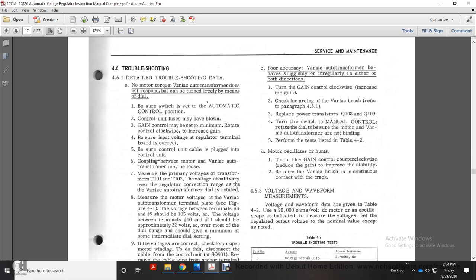Alright, troubleshooting. 4.6.1, detailed troubleshooting data. No matter the torque, variadic auto transformer do not respond, but they can be turned freely with the meaning of the dial. Be sure your switch is an automatic control switch. Control unit fuses may be blown, with the gain control may be set at a minimum. Rotate with the control clockwise to increase the gain. Be sure the input voltage of the regulator terminal board is correct. Be sure control of the unit and cable is plugged in with the control unit. Coupling between the motor and Variac autotransformer may be loose.